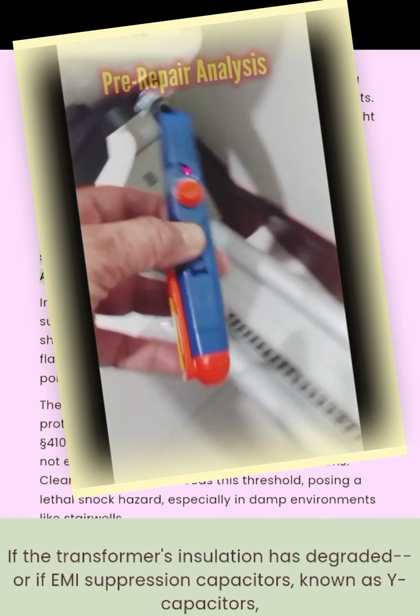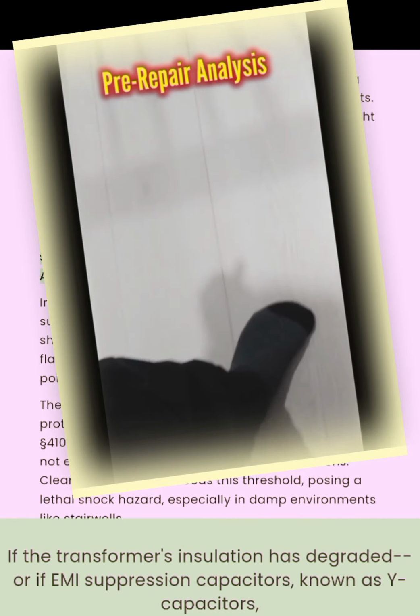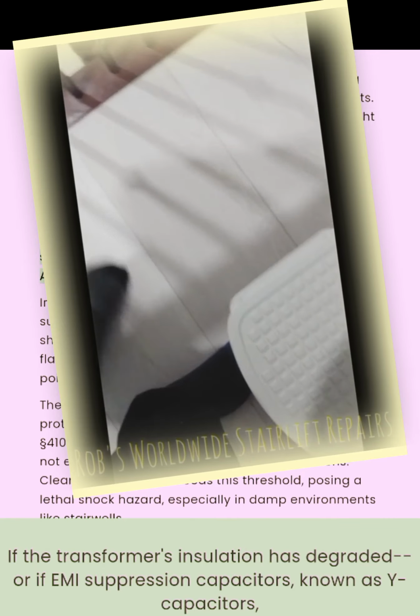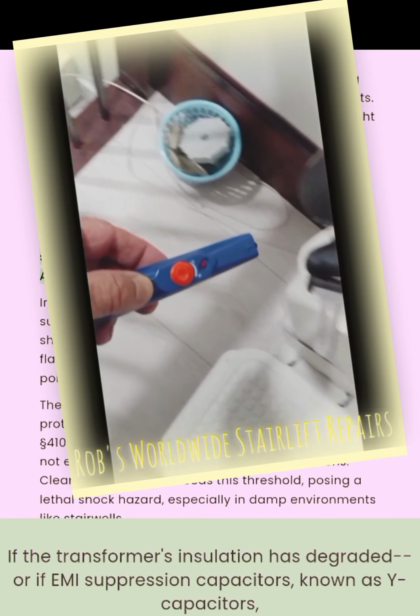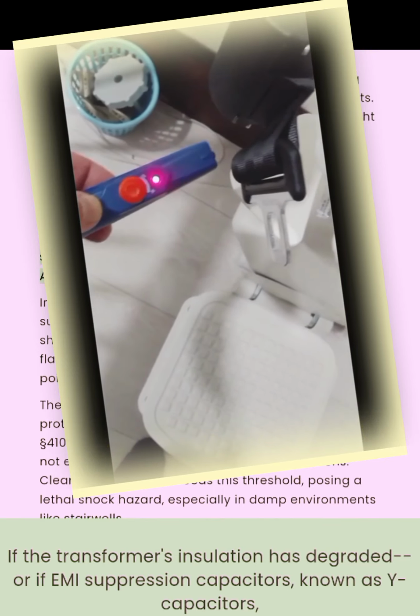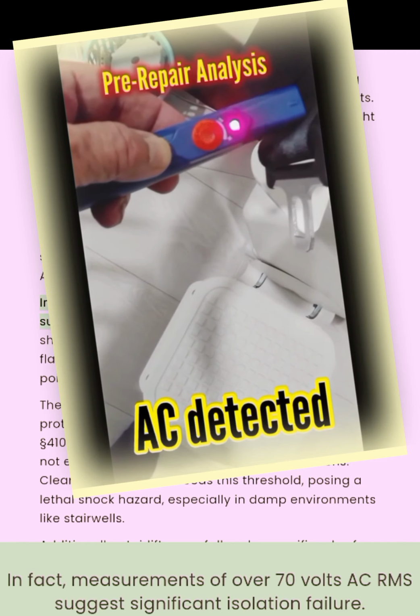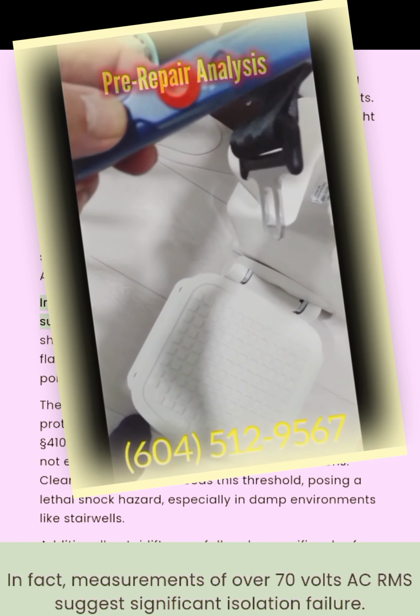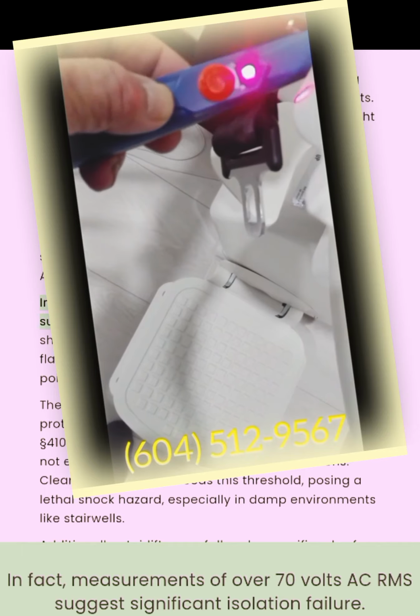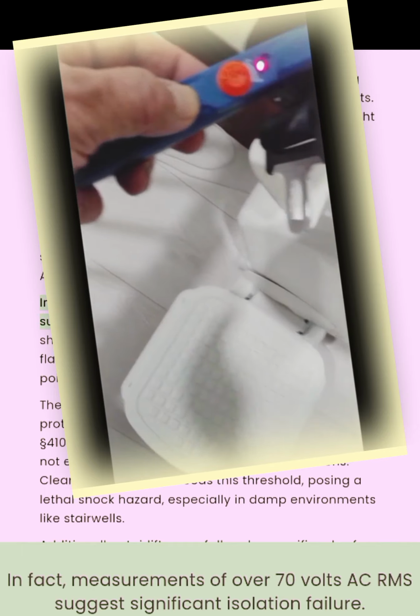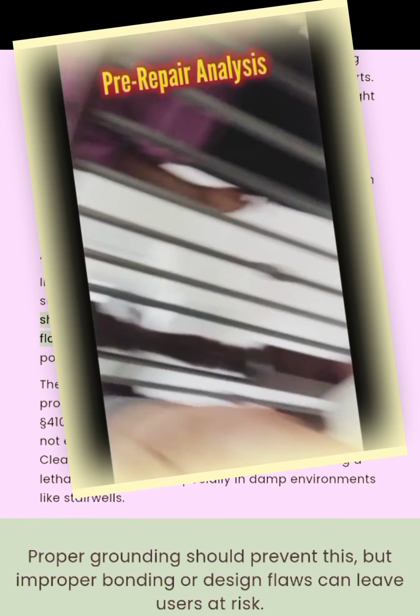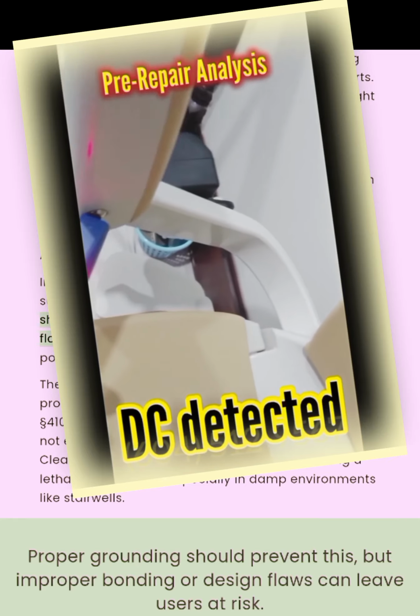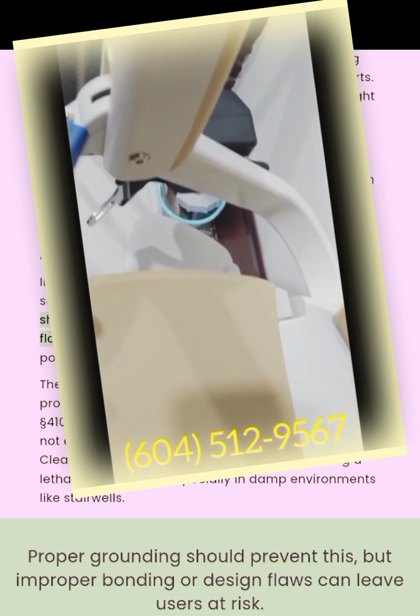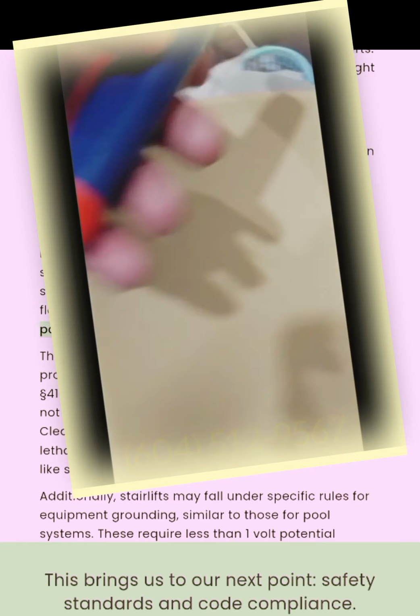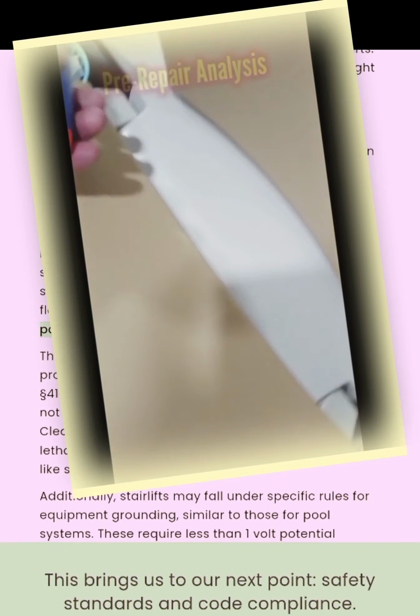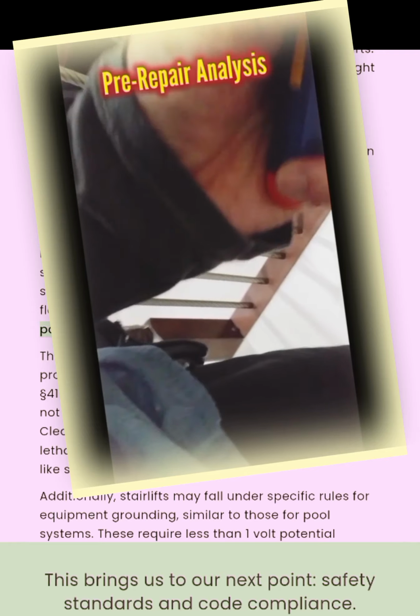If the transformer's insulation has degraded, or if EMI suppression capacitors, known as Y capacitors, fail, AC current can leak onto grounded surfaces. In fact, measurements of over 70 volts AC RMS suggest significant isolation failure. Proper grounding should prevent this, but improper bonding or design flaws can leave users at risk. This brings us to our next point: safety standards and code compliance.